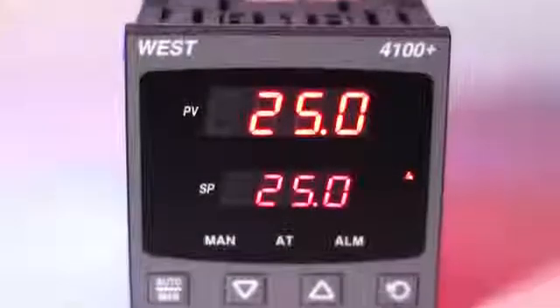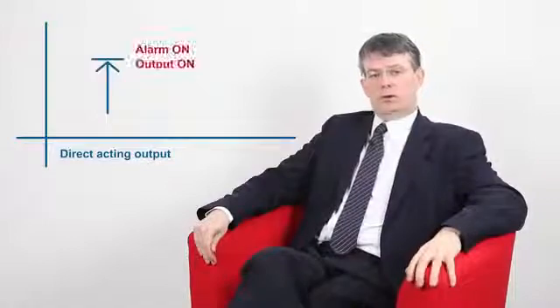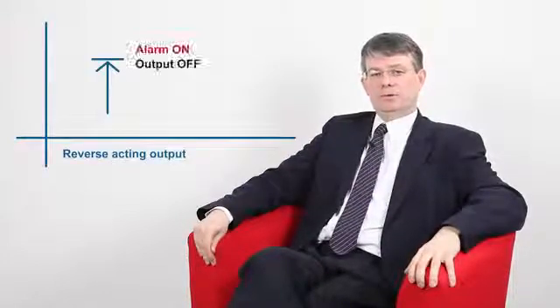When setting up an output to work with one of these alarms, it is important to consider whether to set that output up to be reverse or direct acting. If you previously set up a control output, you would already have come across the terms reverse and direct acting, and with alarms they work in a very similar way. A direct acting output is on whenever the alarm is in the active state and off when it is inactive. A reverse acting output is simply the opposite — when the alarm is active the output is off, and when the alarm is inactive the output is on. An example of where a reverse acting alarm output may be useful is if we had wired a siren to a reverse acting alarm output on a temperature controller, making the process fail safe by wiring the siren to the normally closed contacts of an alarm relay output. This is because we need the relay to be de-energised when the alarm is active and energised when the alarm is not active.